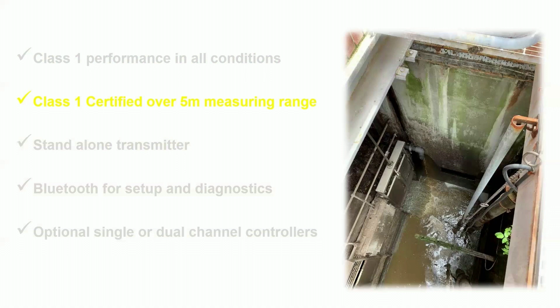Third point I wanted to talk about, and this is touching on and reiterating what Peter was saying, it's a standalone Class 1 transmitter. This really comes into its own in some of the event duration monitoring, sort of UMON3 applications and the requirement for monitoring the lowest spill point to storm tanks. Quite often the location that you need to measure is in a remote location. There's no power. And so it makes it quite difficult to put power in, or it can be quite tricky when you're looking at power consumption of a battery powered system. So these are loop powered transmitters, so we don't have to have a box on the wall to give that MCERTs accurate measurement.